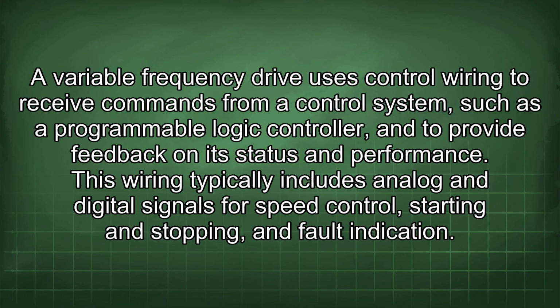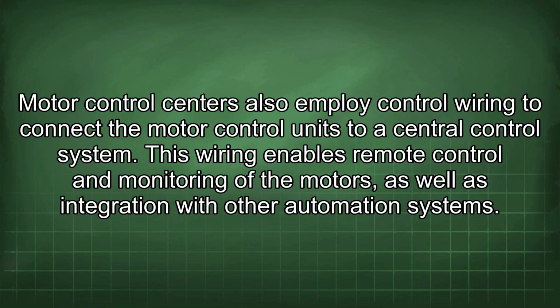A variable frequency drive uses control wiring to receive commands from a control system, such as a programmable logic controller, and to provide feedback on its status and performance. This wiring typically includes analog and digital signals for speed control, starting and stopping, and fault indication. Motor control centers also employ control wiring to connect the motor control units to a central control system. This wiring enables remote control and monitoring of the motors, as well as integration with other automation systems.